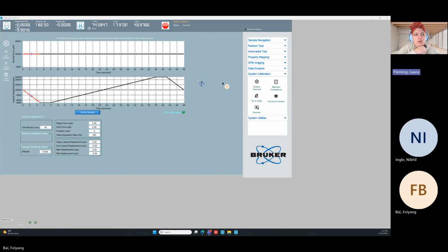When you click Cal Air Scratch, it brought you into the scratch load function screen, which we'll talk about at length. But basically, you just get another graph. We're used to this normal force versus time graph as a load function. Here now we have also lateral displacement and time. So for the Cal Air indent, during the indentation axis calibration, all we do is actuate down and back, and then we calibrate to the springs, knowing that the force felt should be 0. Similarly, here for the scratch axes, we do not move in the normal direction.